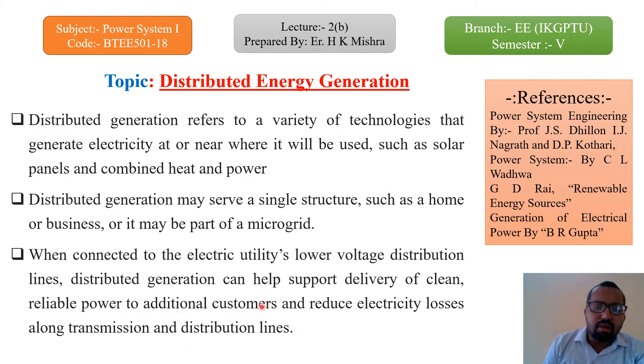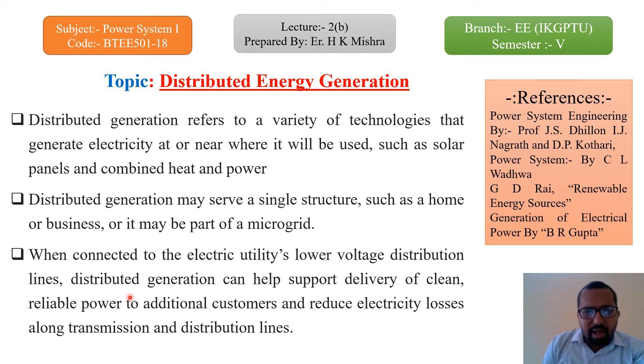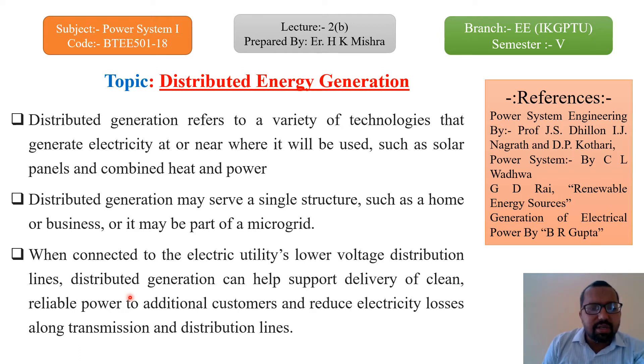Some distribution losses also occur as line losses, and distributed generation should reduce those as well. When supply comes from a far area, around two or three kilometers along the distribution line, the voltage level at the last end of the location is too low and the power quality is very poor. When we connect distributed generating systems within the distribution system and synchronize them, the power quality will be improved.